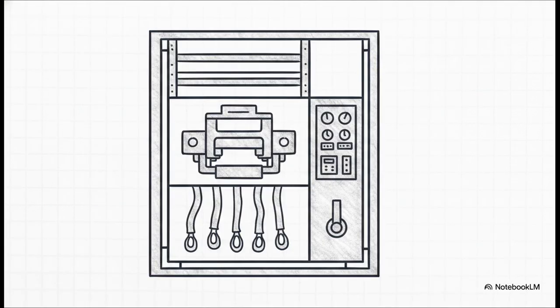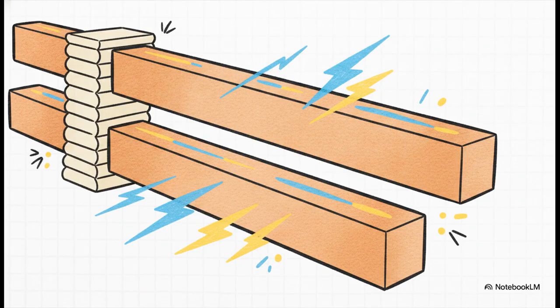So how do they actually pull off this fault containment in the real-world hardware? Well, every metal-clad board is built using 5 core compartments every single time. You've got the bus bar, the circuit breaker, the cable terminal, the secondary equipment, and the operating unit. Let's do a quick step-by-step breakdown of this anatomy so you know exactly what's going on inside each of these isolated rooms. First up, compartment number 1, the bus bar compartment, housing the copper bars.